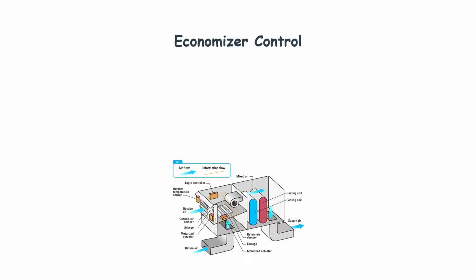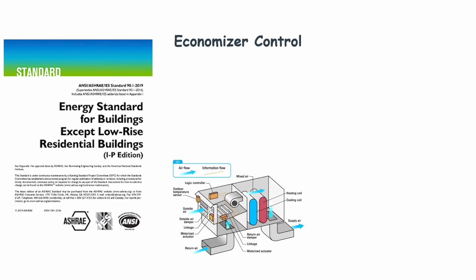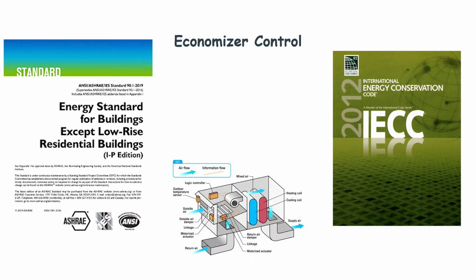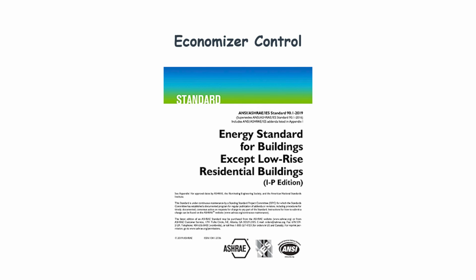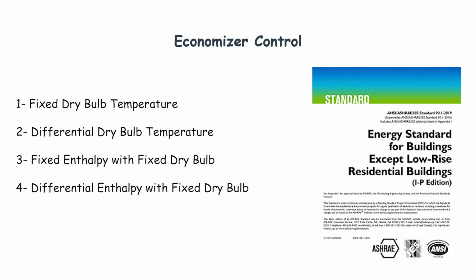Here's the biggest question about the control of economizers. When does the mechanical system need to switch into the economizer mode? There are multiple methods for the control of economizers. These methods are listed in energy standards and energy codes such as ASHRAE 90.1 and the International Energy Conservation Code. But here, I'm going to focus only on the prescriptive methods that are allowed by ASHRAE 90.1 because this standard is widely adopted by energy codes. The four methods are shown here on the screen, and I'm going to go over each of them.